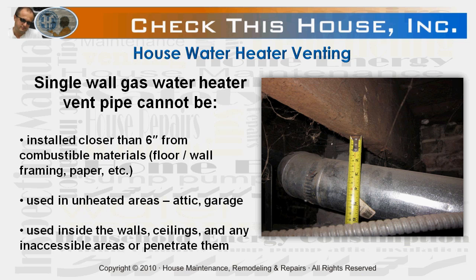Now a few no-no's. Number one: a single wall gas water heater vent pipe cannot be installed closer than 6 inches from combustible materials such as floors, wall framing, paper, etc. Such installation could create pyrophoric conditions and a fire hazard. A pyrophoric condition is when a material ignites spontaneously at a significantly lower temperature if it is constantly exposed to heat. So if something would normally ignite at 500 degrees Fahrenheit, by applying constant heat to it, that ignition point might be lowered to, say, 250 degrees Fahrenheit.